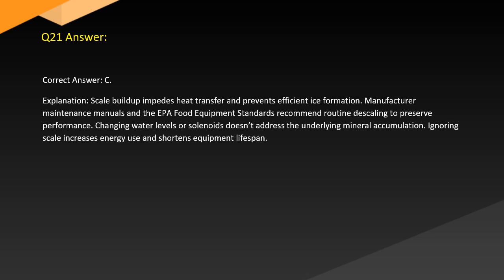Answer. Correct answer. C. Explanation. Scale buildup impedes heat transfer and prevents efficient ice formation. Manufacturer maintenance manuals and the EPA food equipment standards recommend routine descaling to preserve performance. Changing water levels or solenoids doesn't address the underlying mineral accumulation. Ignoring scale increases energy use and shortens equipment lifespan.